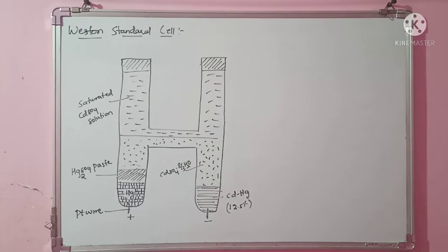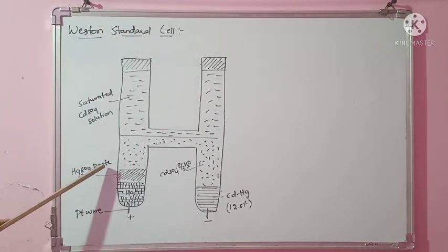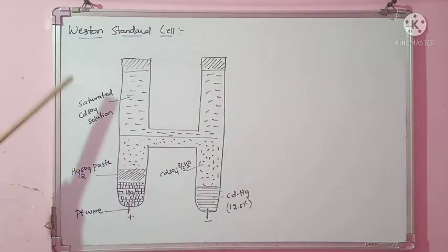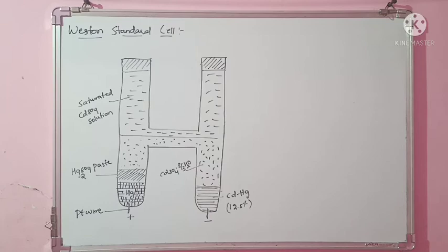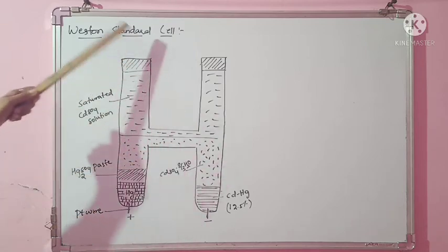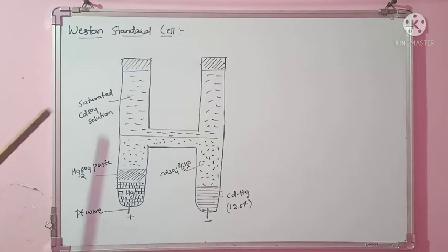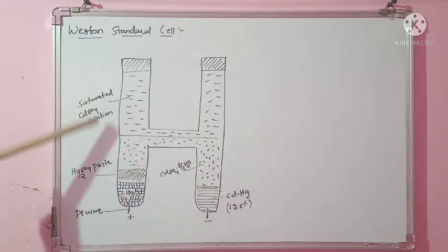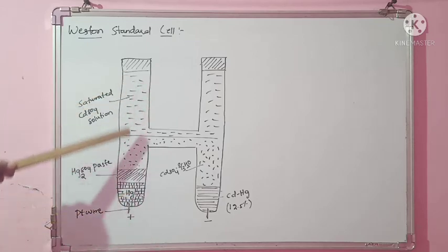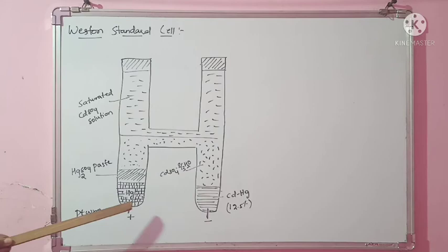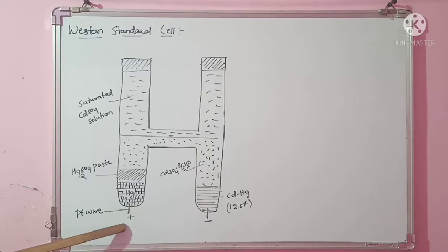Now let us understand in detail how the Weston standard cell is constructed. Here you can see the Weston standard cell. This cell satisfies the conditions of a standard cell. As you can see, it is in the form of an H shape — it looks like the letter H. One limb consists of mercury, which serves as the positive electrode.